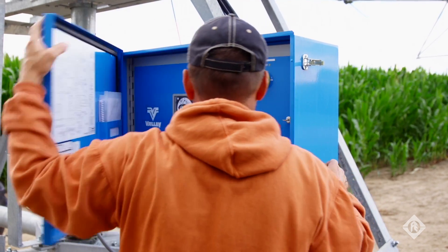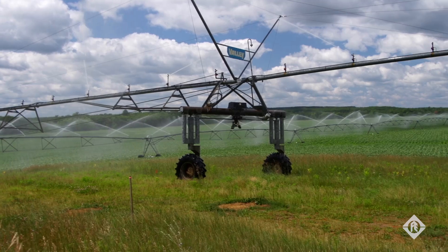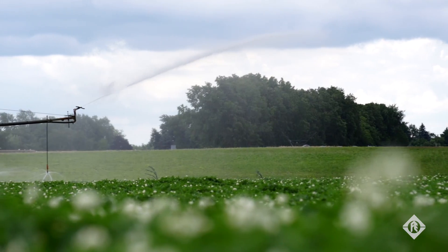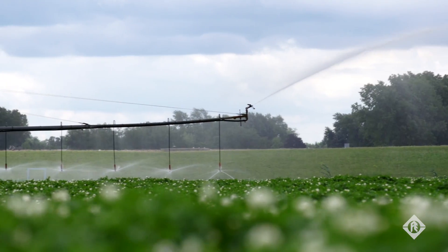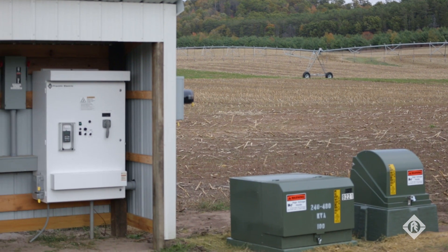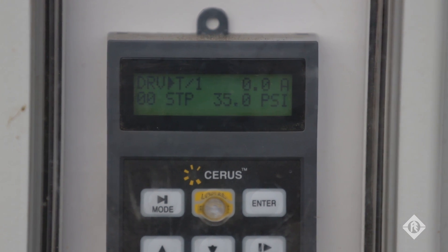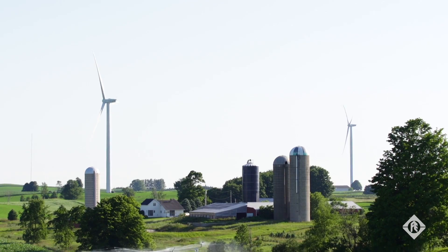The technology in the last 10 years has just been unreal, whether it be with our auto-steer tractors and the technology that Franklin's come out with — VFD drive systems for motors to only use the amount of pump that we need at the times we need it. The power company gets really antsy when you're trying to put a big motor on a single phase system. And when you call them and say I am putting a variable frequency drive on, then that makes them more comfortable. It gives you the soft start capability. It does the conversion inside without having a rotary phase converter, and I can put the bigger horse on to meet the demands of the system.